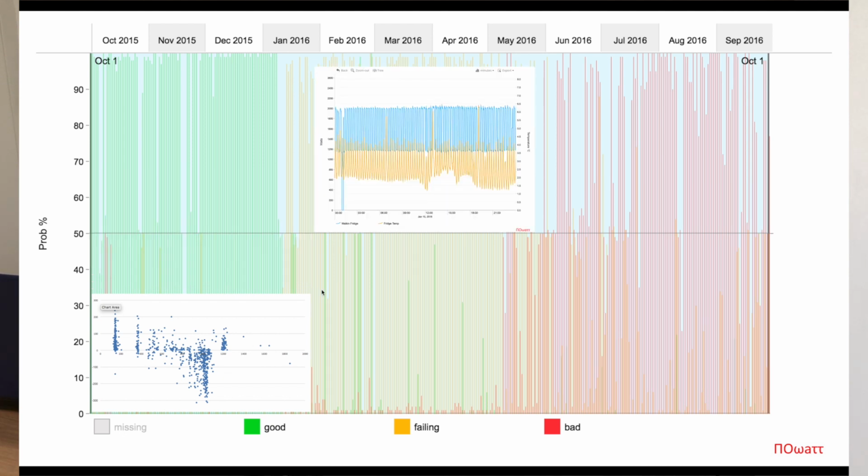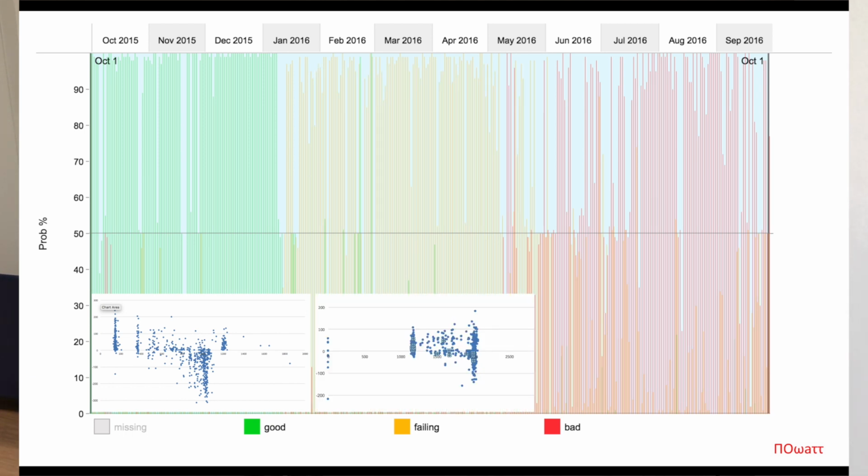And that's another one. This one here now looks very similar, but you'll notice that the on-off of the compressor has a base on it. It's constantly at 1200 watts. So even though the temperature is going up and down with the compressor, from the operator's perspective, they wouldn't know anything was wrong at all, because they don't measure the individual consumption of these fridges most times. So as far as they're concerned, this is working perfectly.